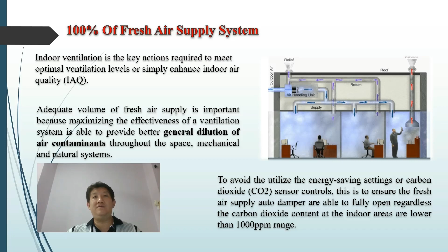In order to provide 100% full fresh air supply to the internal space area, it is advisable to avoid the utilization of energy setting or carbon dioxide sensor control. This is to ensure the fresh air supply auto damper is able to fully open regardless of the carbon dioxide content in the indoor area, which is lower than the 1000 ppm range.